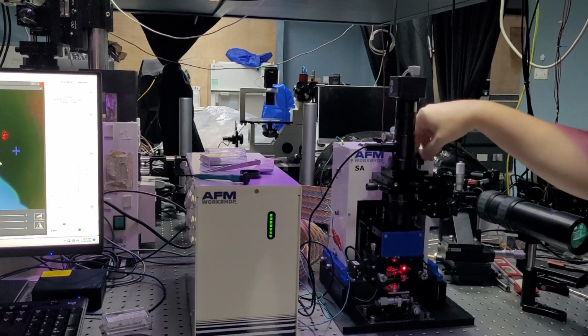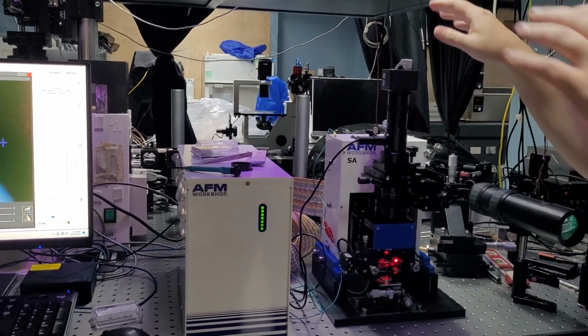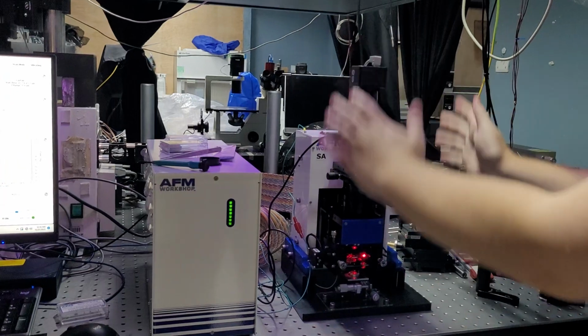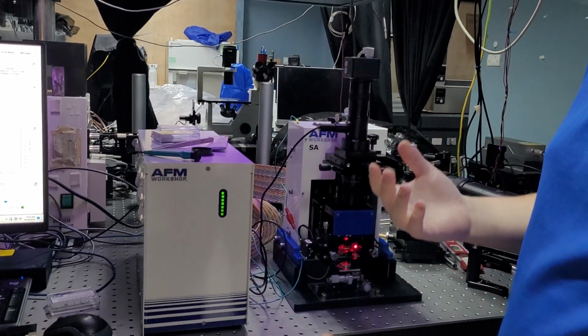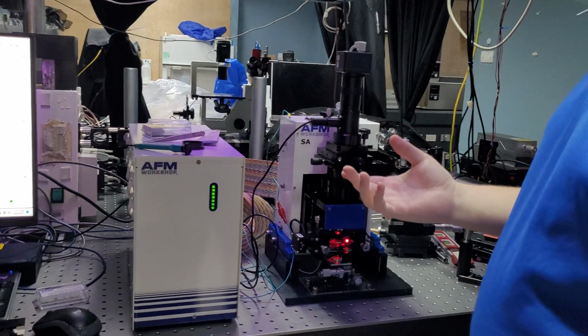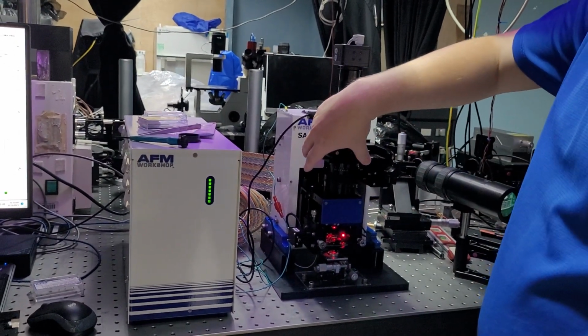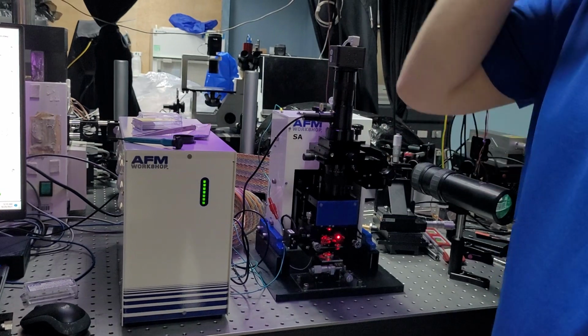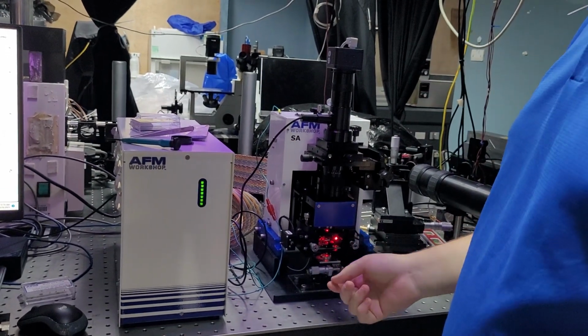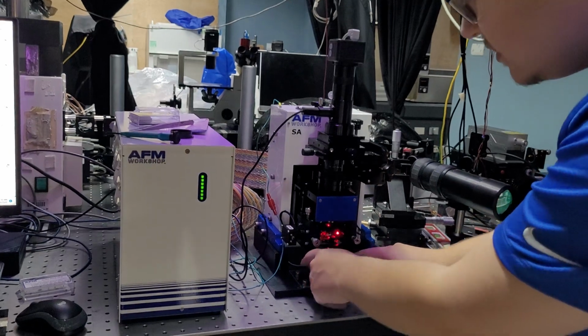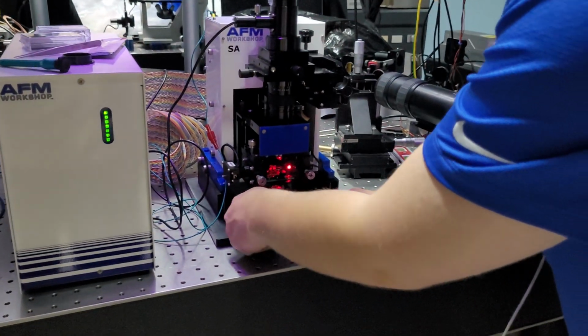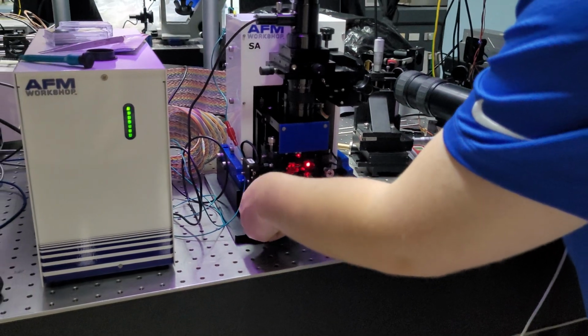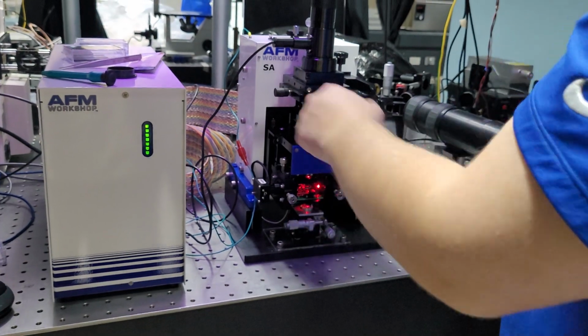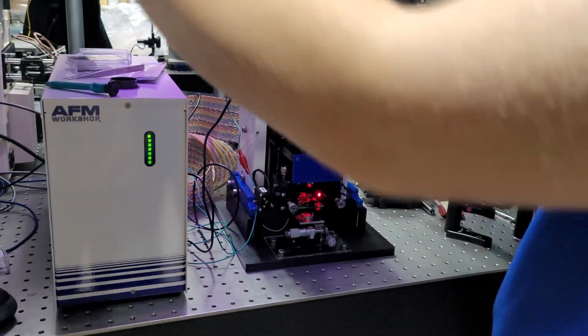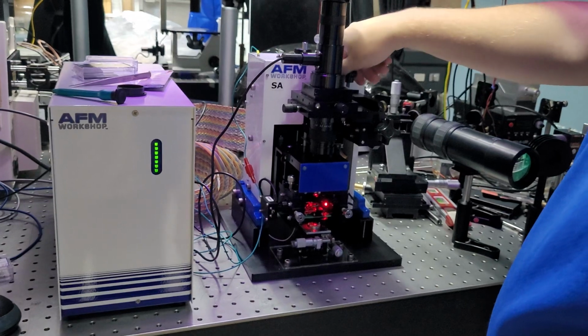And then continuing to go down, and we'll cover this again. I just want to give you kind of a basic overview of the AFM, the things that you can manipulate, the things that you should not manipulate. I also didn't say this. You should not need to manipulate the camera controls, really. If you put a new sample in and you want to look at it, use these at the bottom, which, if you look, this moves the sample. So if you want to look around on your sample, please use these. Do not use these, because right now we're set in a position where we can perfectly see the cantilever.